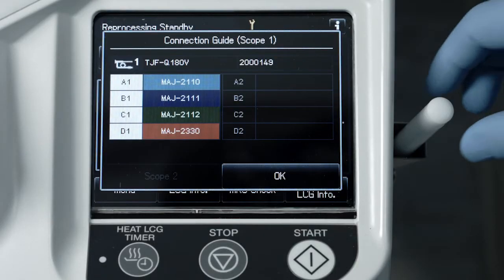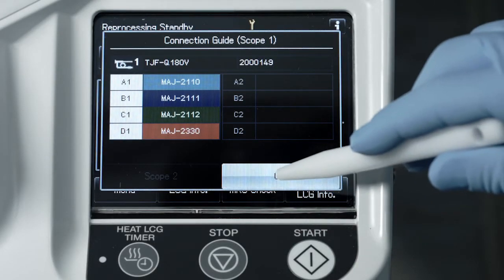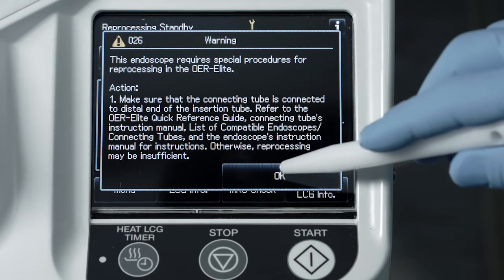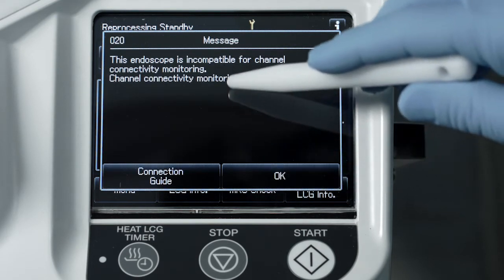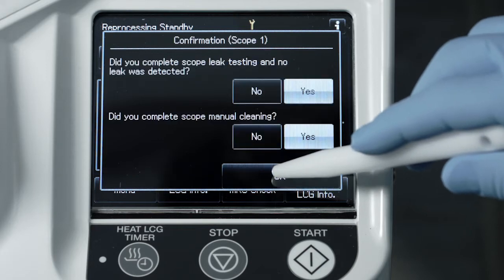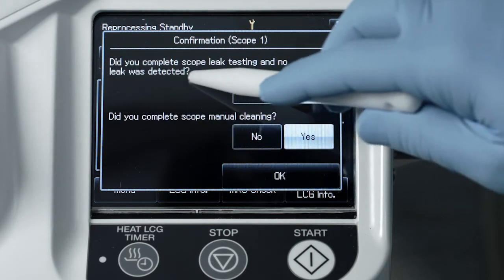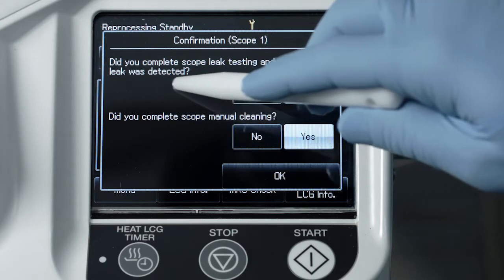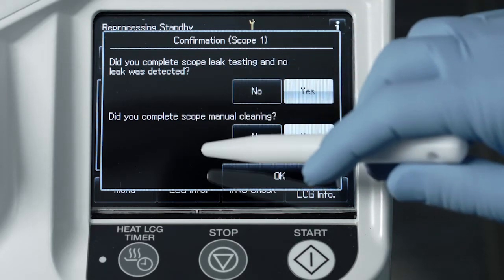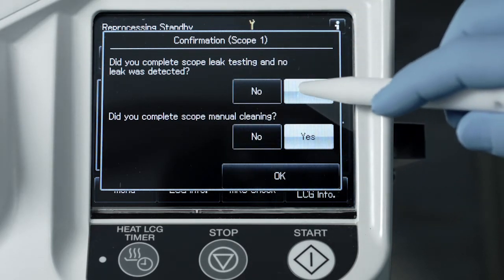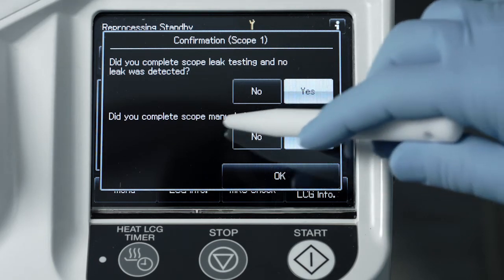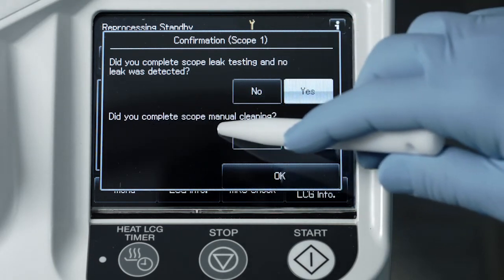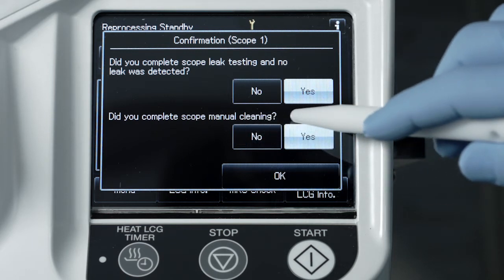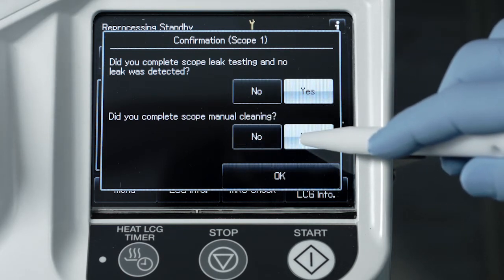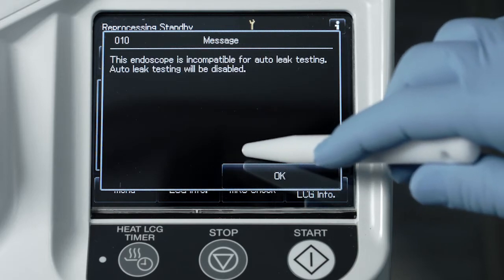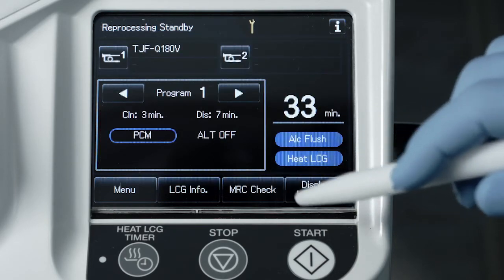Now, make sure to confirm that both the leak test has been performed with no leaks detected and that manual cleaning has taken place with this endoscope, as mandated in the scope's reprocessing instructions. If these required steps have not been performed, please refer to your endoscope's reprocessing instructions in order to complete the reprocessing steps necessary prior to the scope's entry into the OER-Elite. Once completed, press the OK button on this confirmation screen, followed by OK once again.